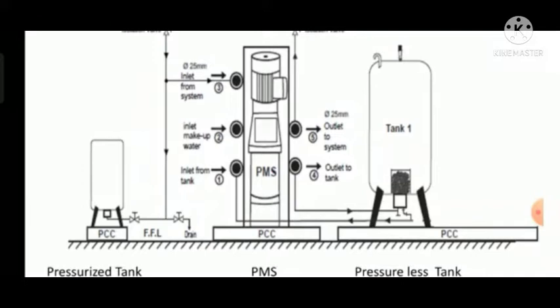Now the first thing is mounting of these three components. All these are mounted on a PCC structure, almost on the same line. If you see here, point 1 is the inlet from the unpressurized tank, then point 2 is the inlet from makeup, which will be by others. The makeup tank will be supplied by others, and point number 3 is the inlet from this header. Moving to points 4 and 5, 4 is the outlet point from this pump, which will go inside the unpressurized tank from one direction, which will be clear in another schematic.